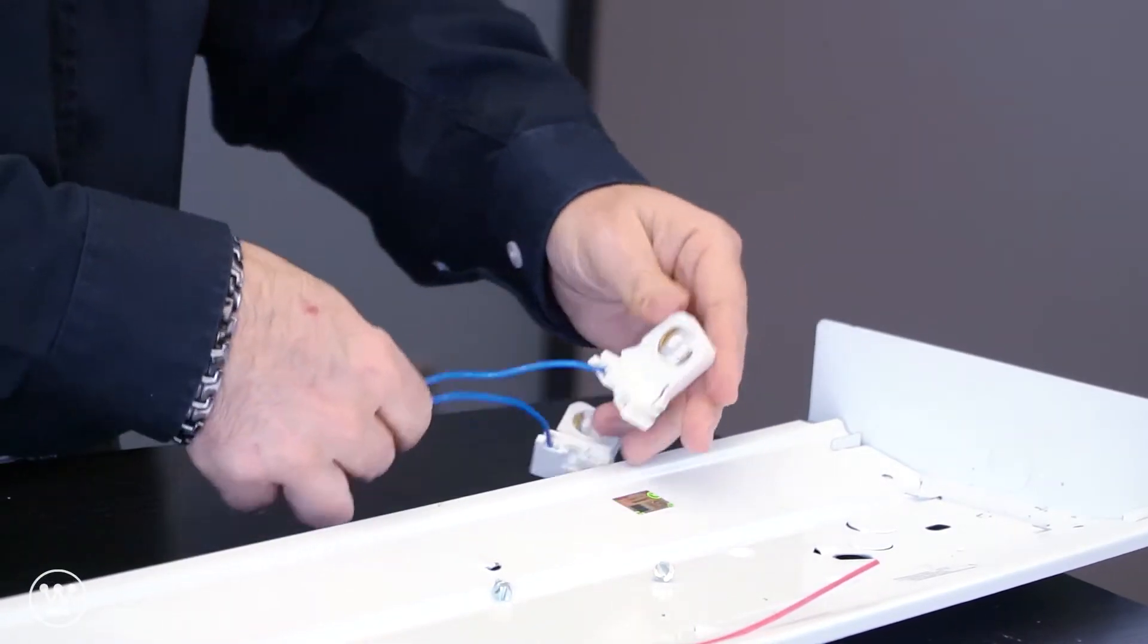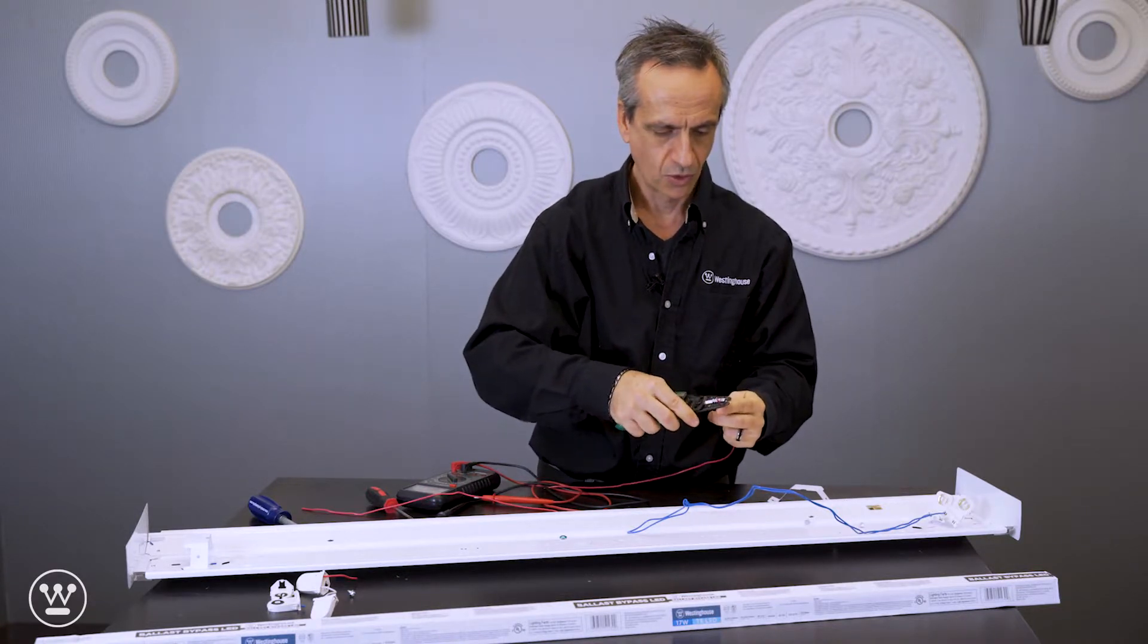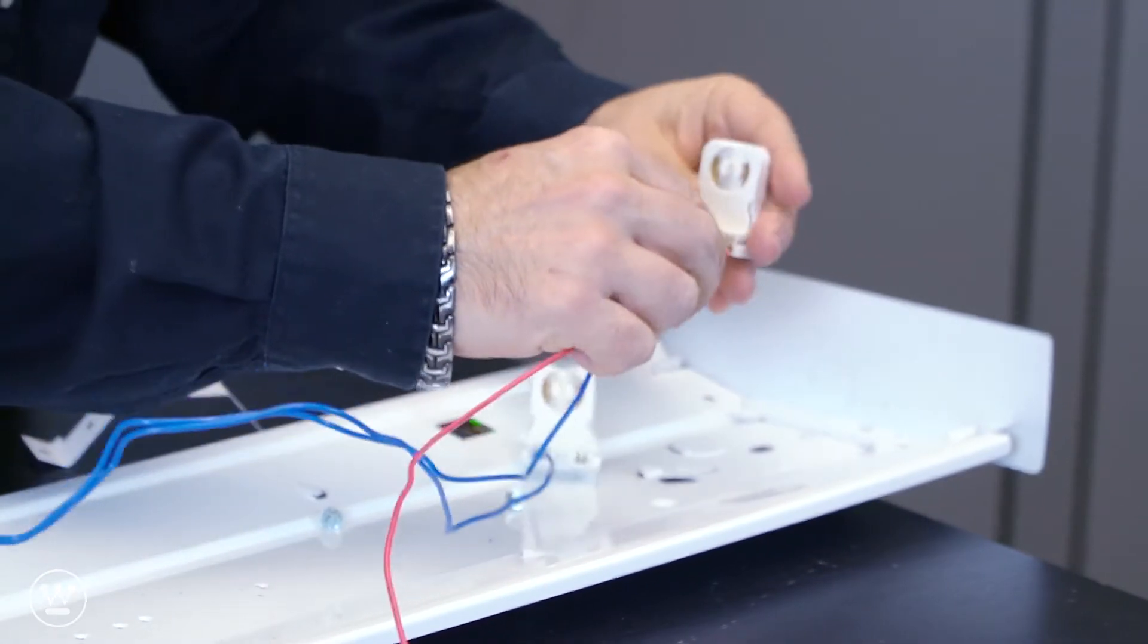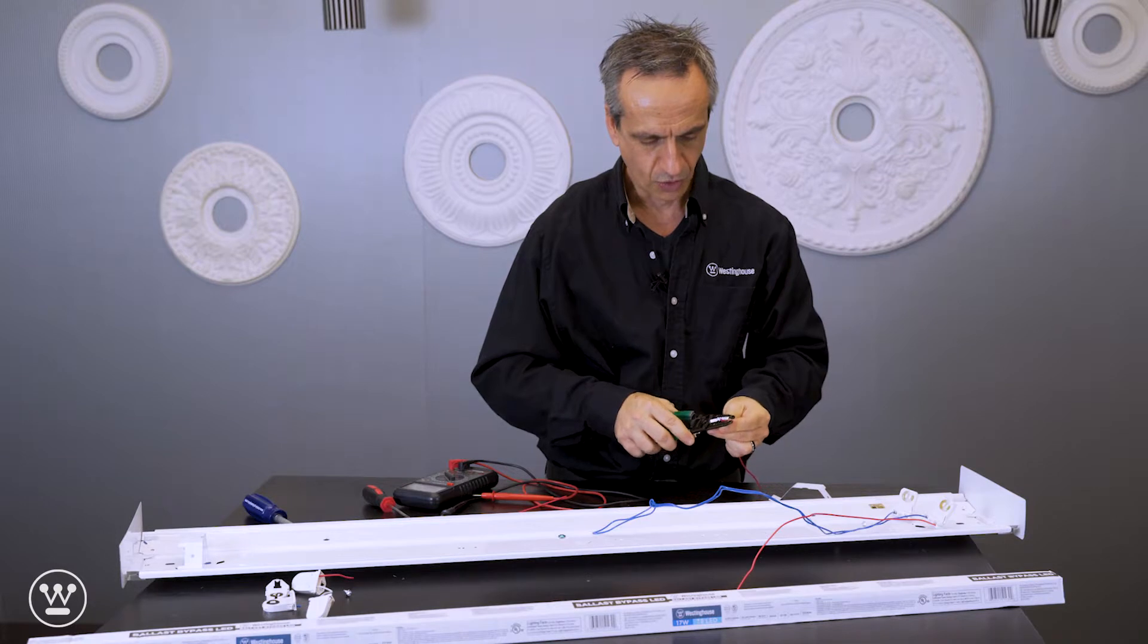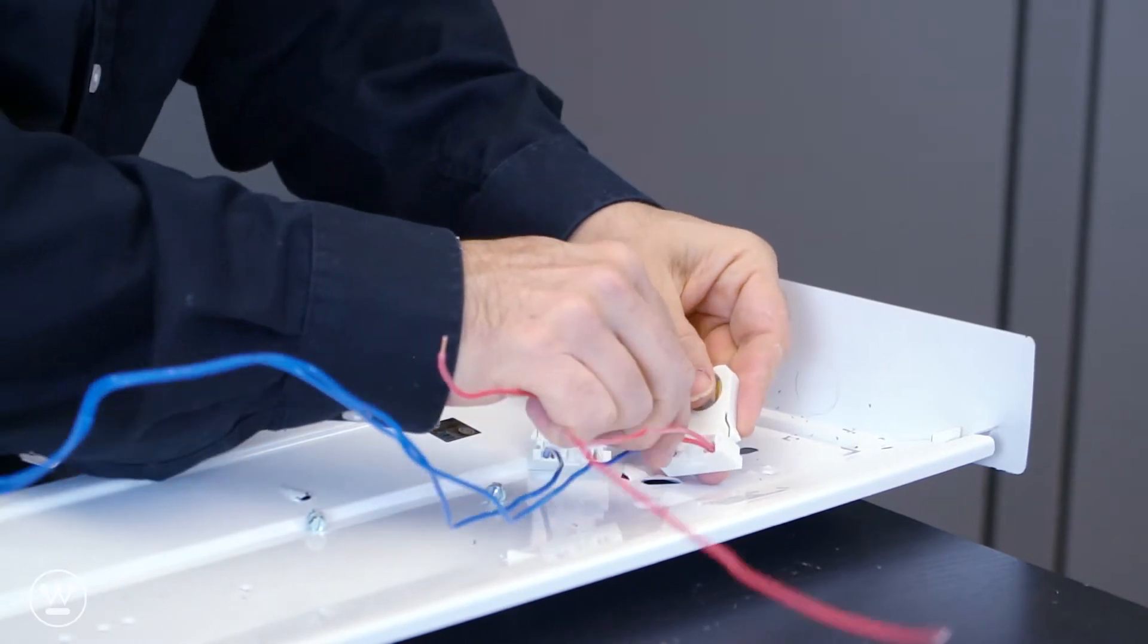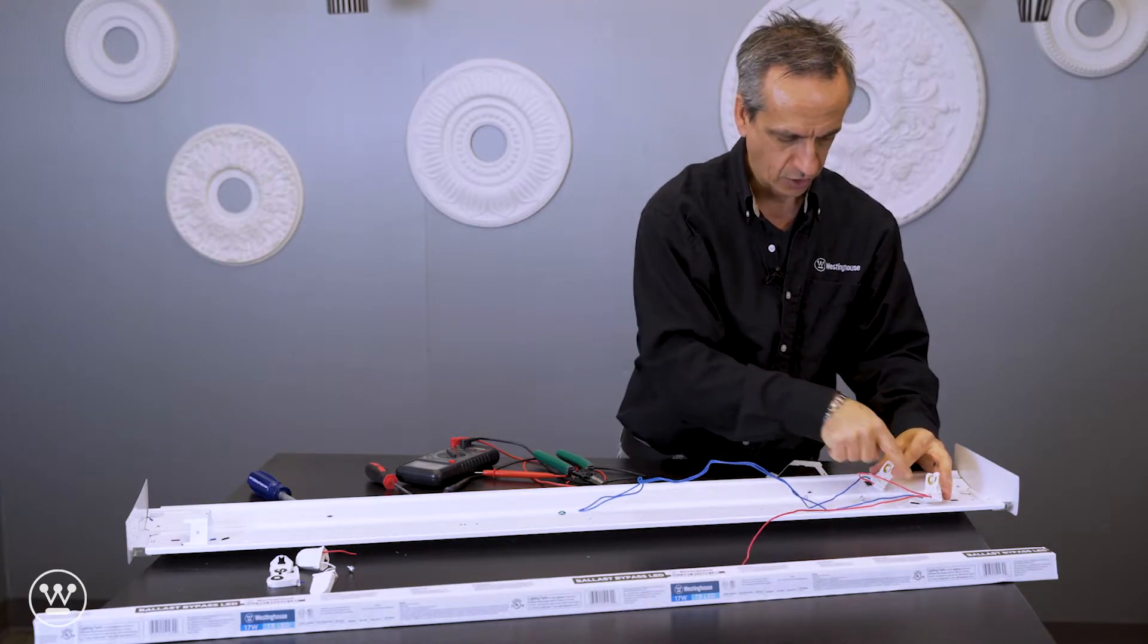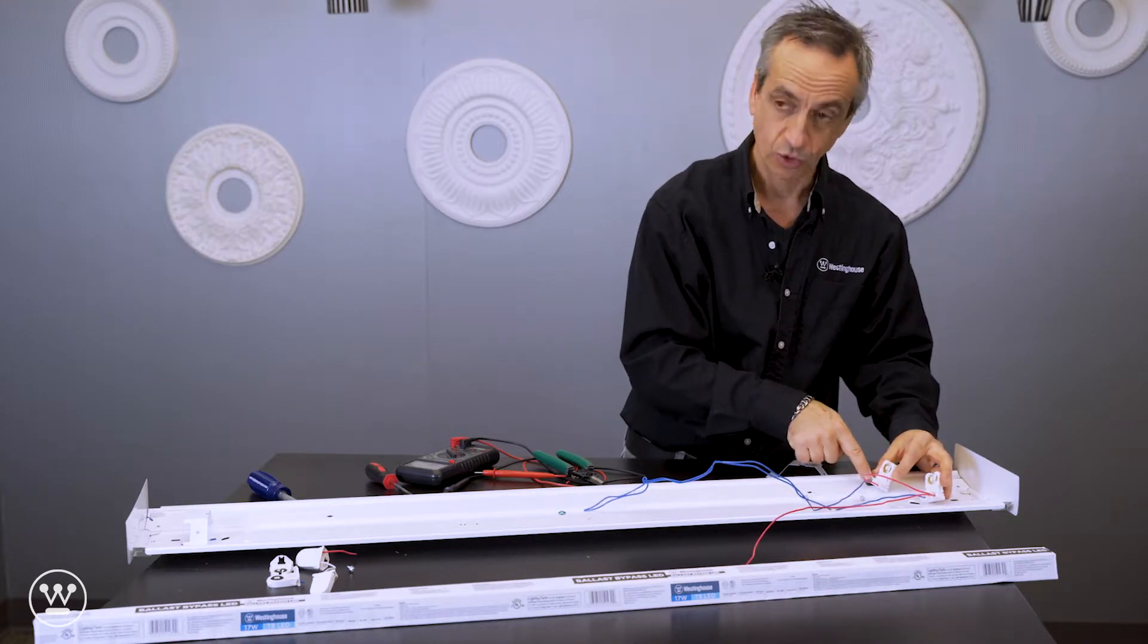We want to make sure that you keep the polarity the same. We're going to strip the red wire which will be feeding the other end of the tombstone. We want to have a jumper wire to go from one tombstone to the next. So now we have the red wire going on one side and blue wire going on the opposite side. And the jumper goes red wire on one side and blue wire on the other side.